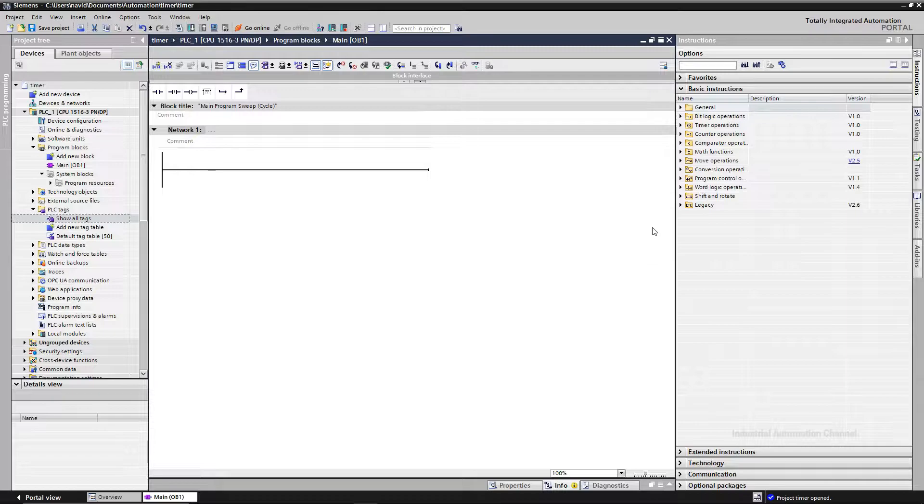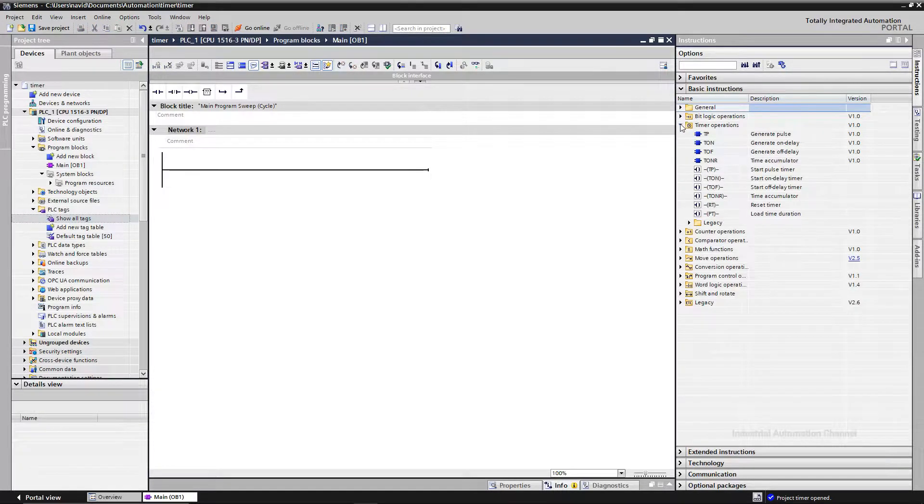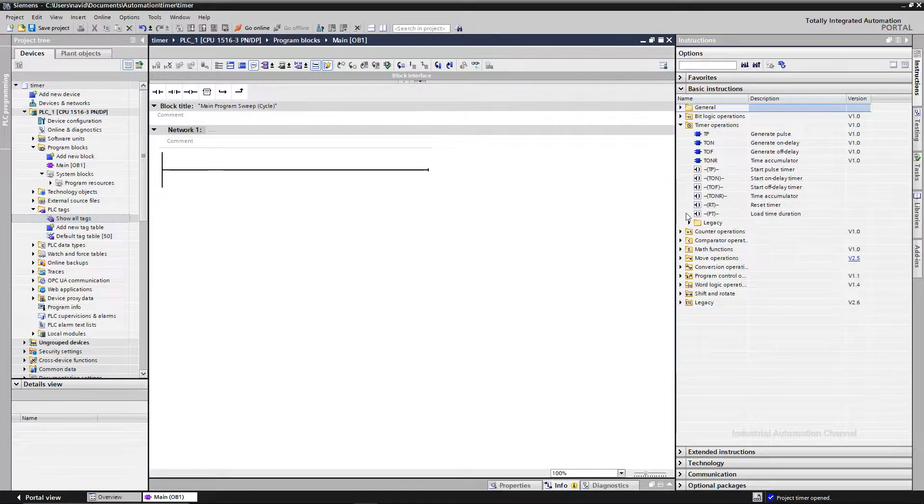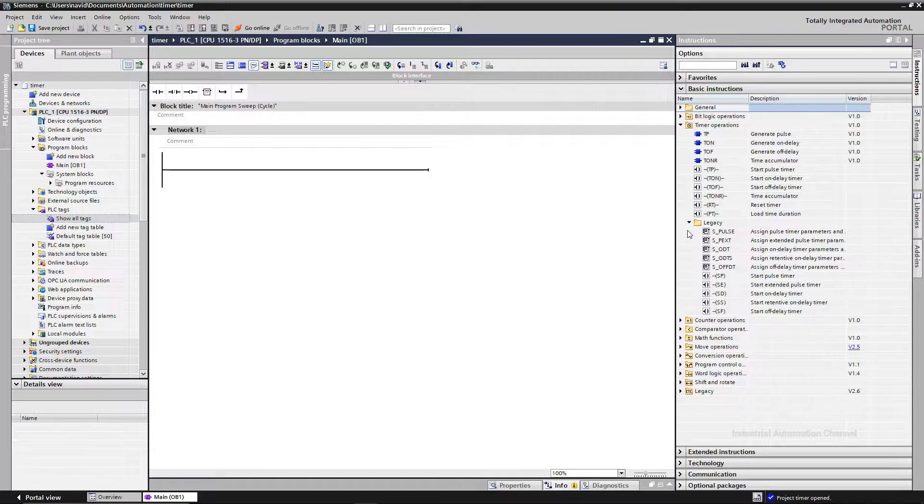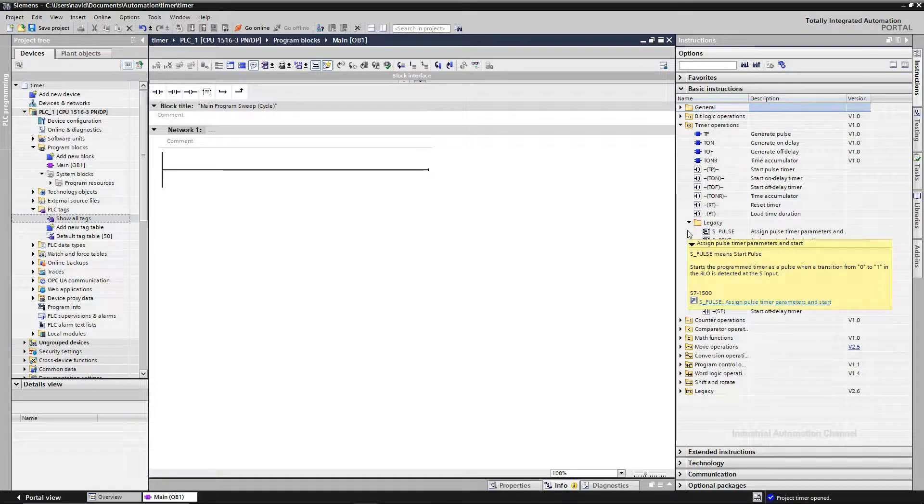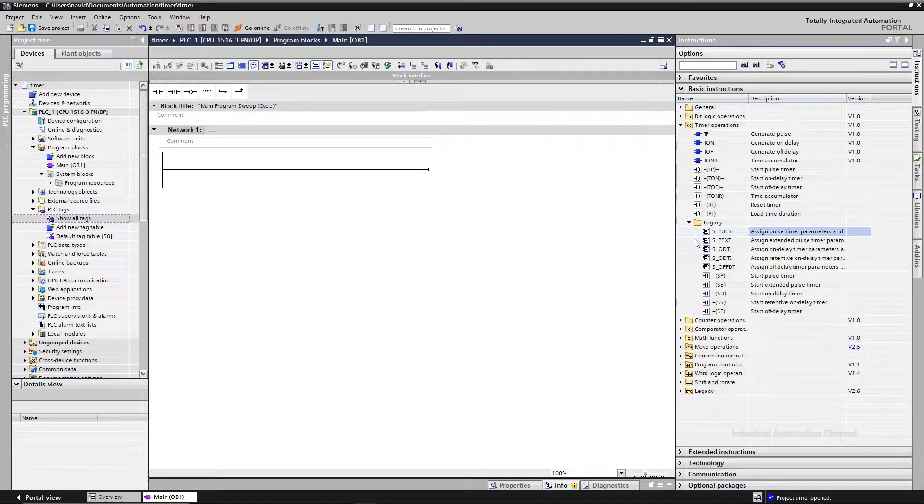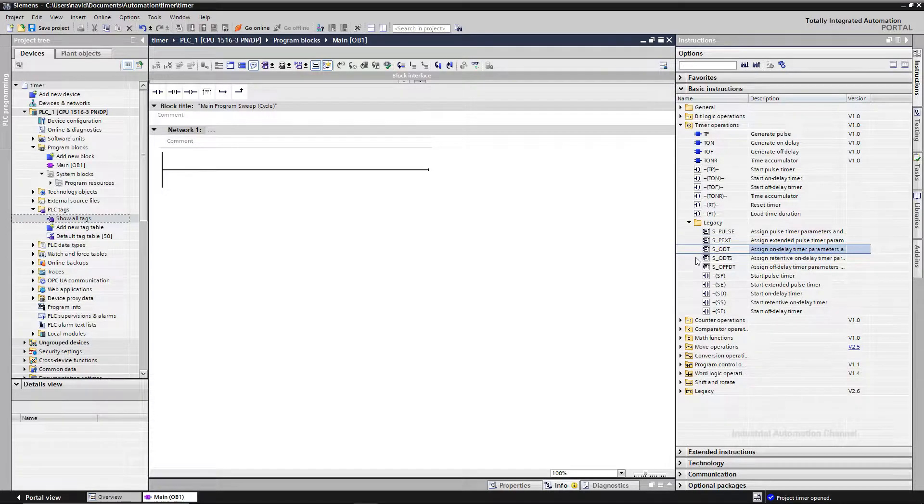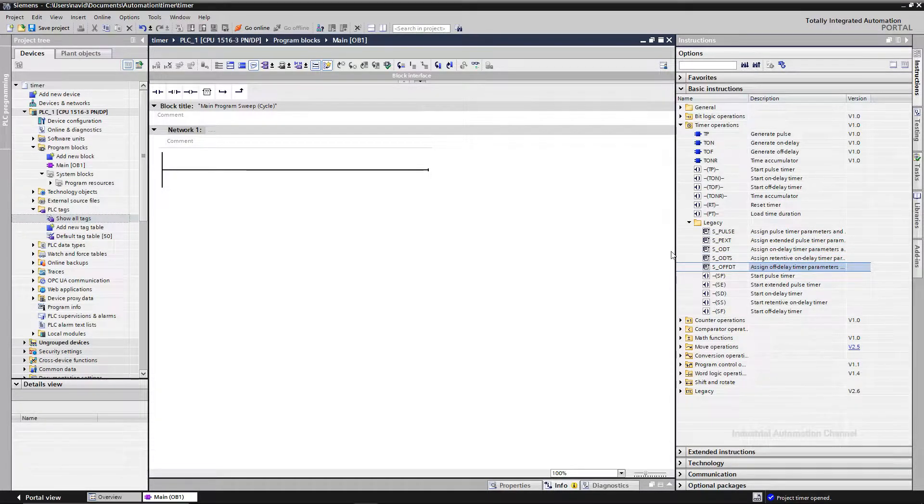There are two types of timers in S7 controller family, the S5 and IEC timers. The S5 timers are from the SIMATIC S5 era. Both S5 and IEC timers can be programmed in the S7 300 and 400 controller families. The same applies to the new S7 1500 family, but only IEC timers can be programmed in the S7 1200 controller and these PLCs are not compatible with S5 timers.